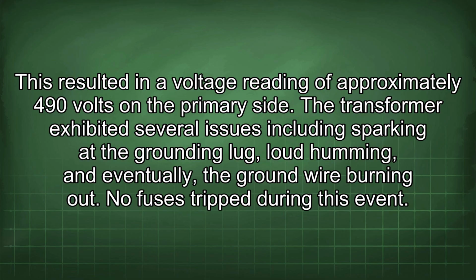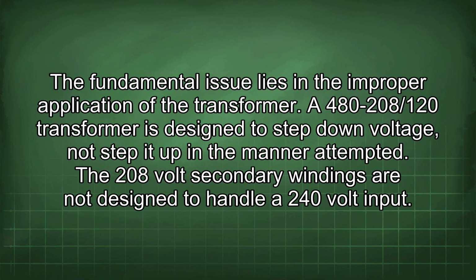The transformer exhibited several issues including sparking at the grounding lug, loud humming, and eventually, the ground wire burning out. No fuses tripped during this event. The fundamental issue lies in the improper application of the transformer. A 480-208/120 transformer is designed to step down voltage, not step it up in the manner attempted.